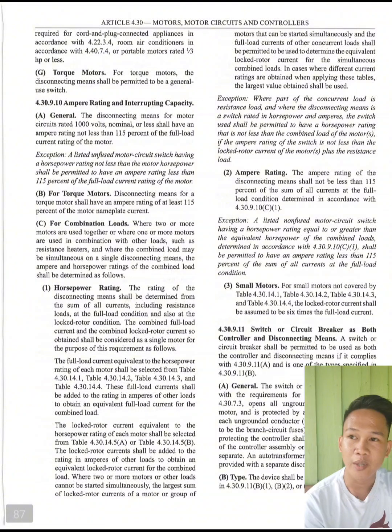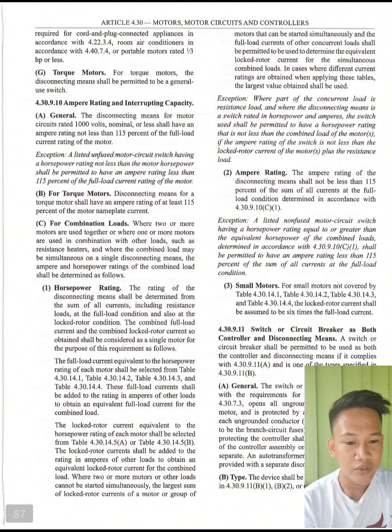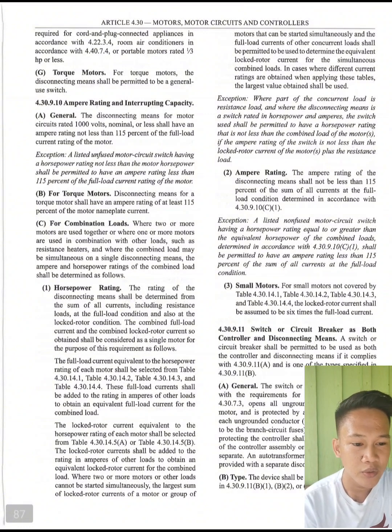So, exemption. Exemption: where part of the concurrent load is resistance load, and where the disconnecting means is a switch rated in horsepower and amperes, the switch used shall be permitted to have a horsepower rating that is not less than the combined load of the motors, if the ampere rating of the switch is not less than the lock rotor current of the motor plus the resistance load.